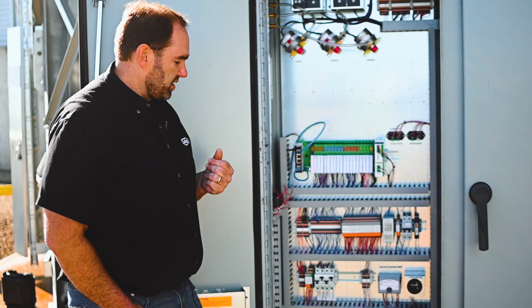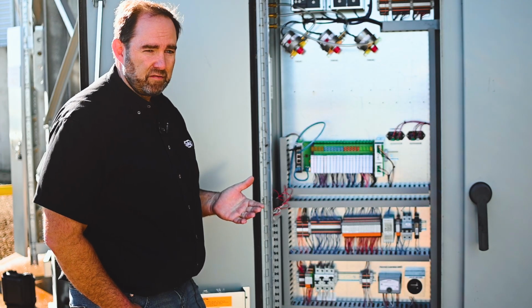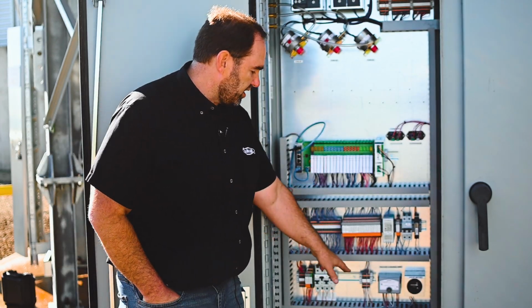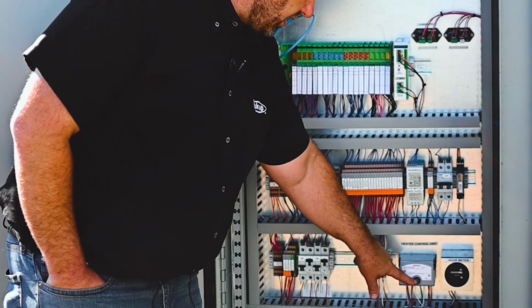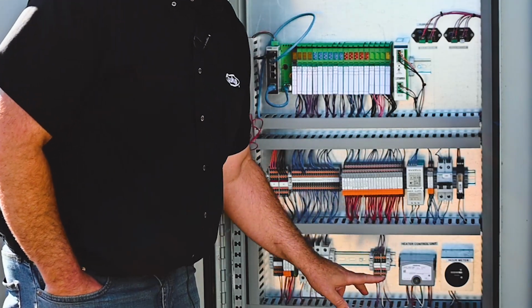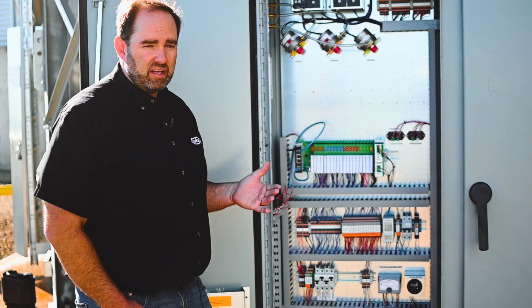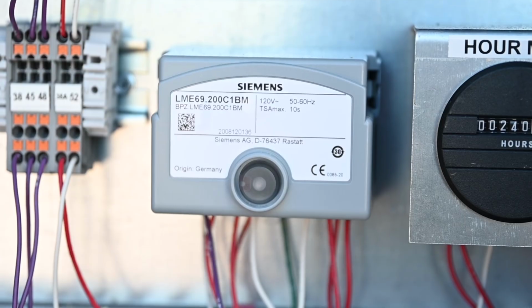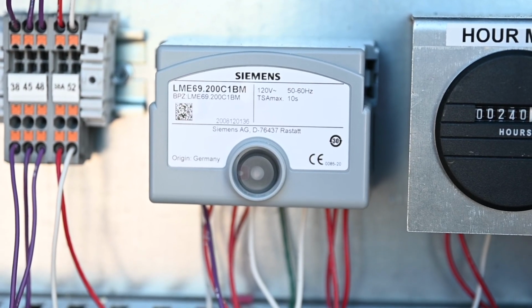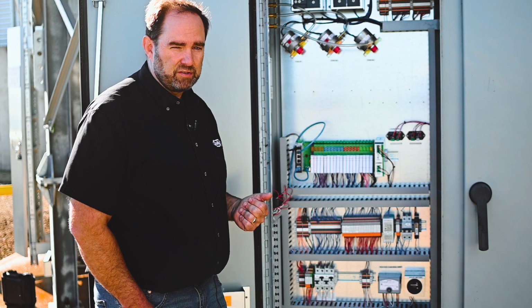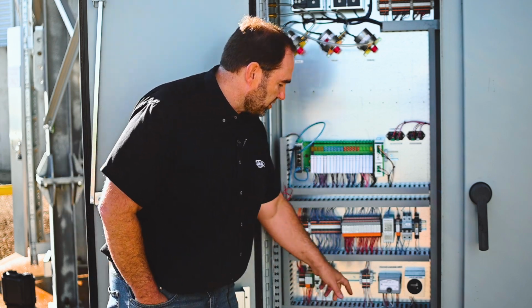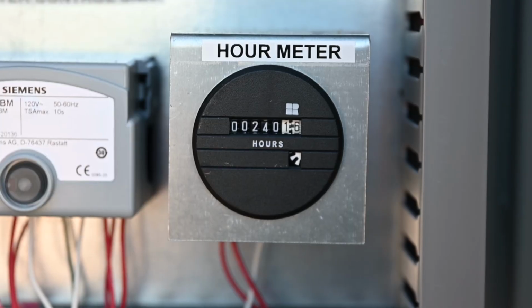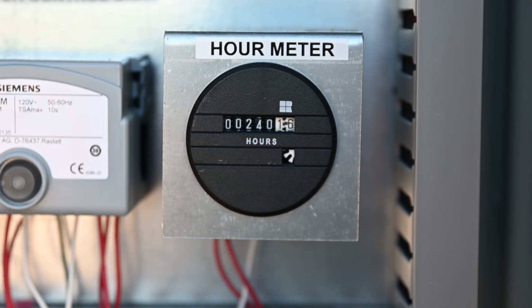So sometimes at startup, it may not light the first time, and if this does fault out and it'll be red on here, you need to press and hold this button for 1 second. Don't press it longer than that, or you can get into a diagnostic mode, which we don't want to be. If we just press it for a second, the red light should go out, and then we can retry to fire our heater. We also have an hour meter that just measures hours of the fans or of the blowers in the dryer.